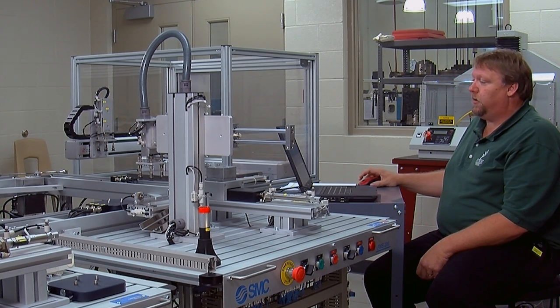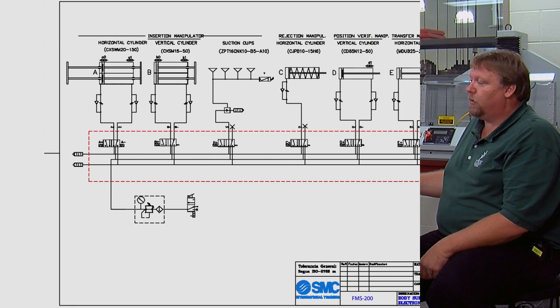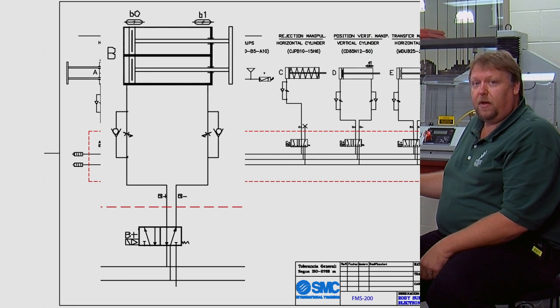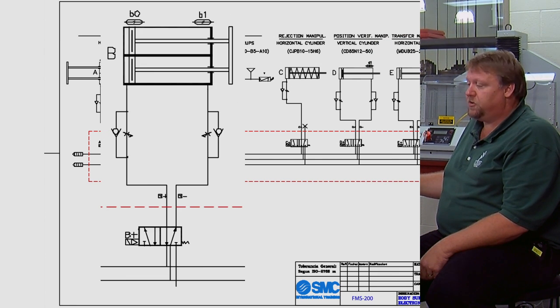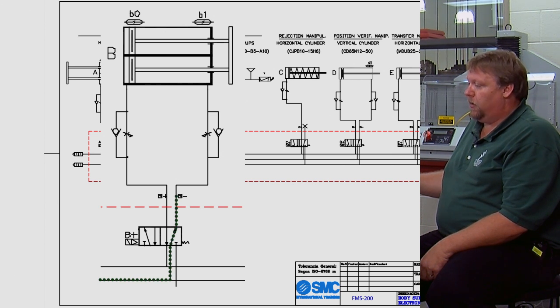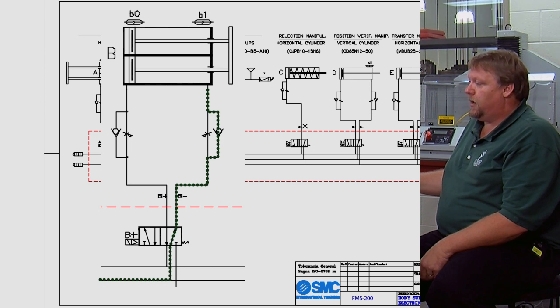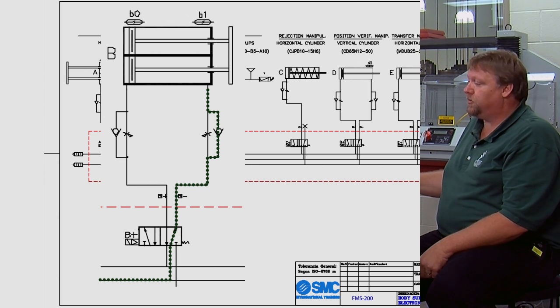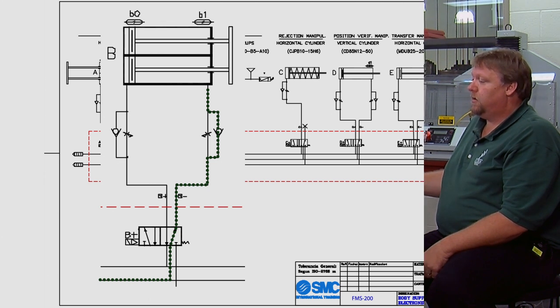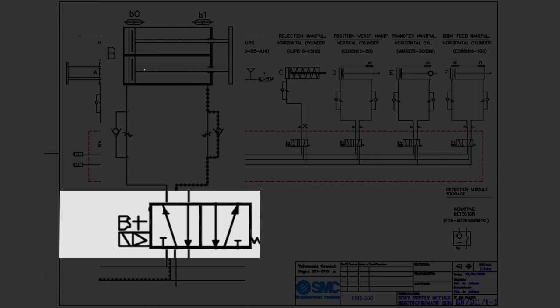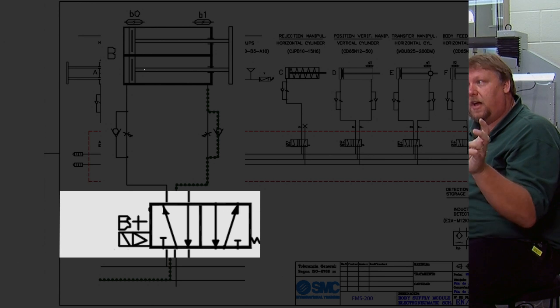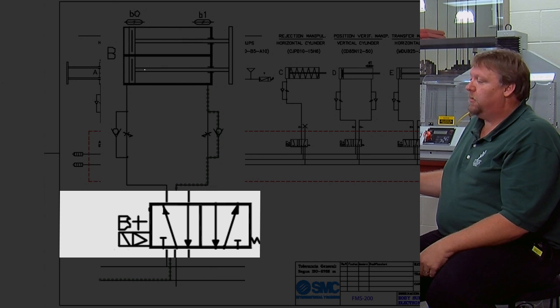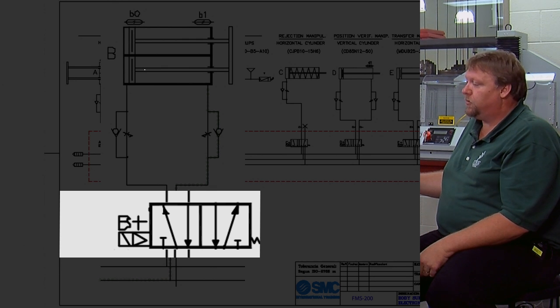Okay so the next cylinder that we want to look at is our vertical cylinder. And notice that it still has two positions just like all the other ones. If we follow the air path to it, we follow it along here, it goes through the valve and forces it to be retracted. This cylinder is shown in a retracted position in its natural state. So with this valve here it takes an electrical signal to extend it. So if we were to apply 24 volts to this coil we can force this box to shift over, or actually the spool inside the valve is what actually does the shifting, but then the flow paths would be reversed.